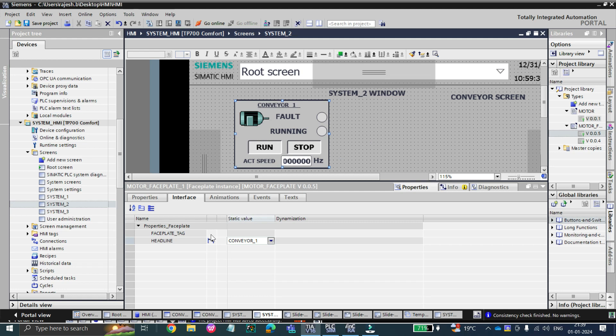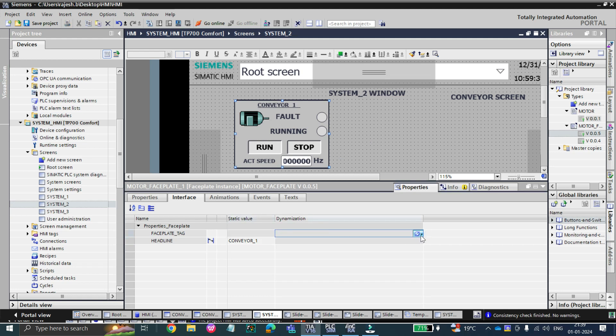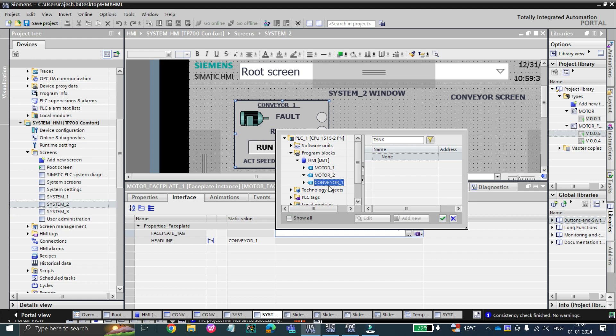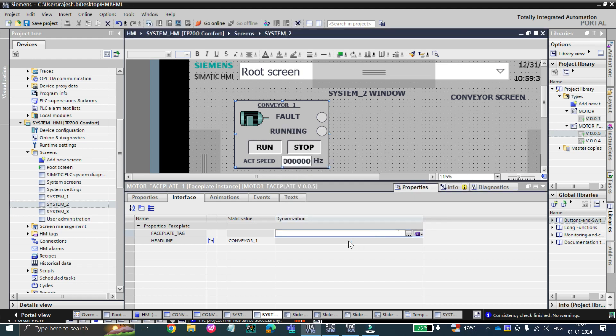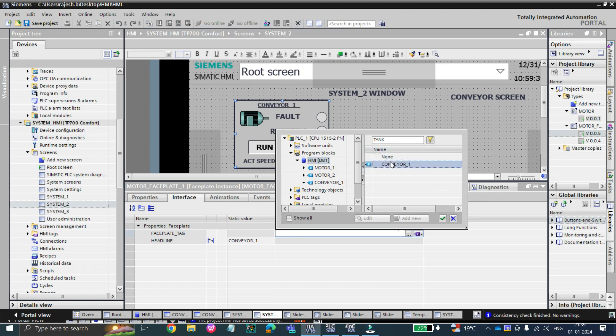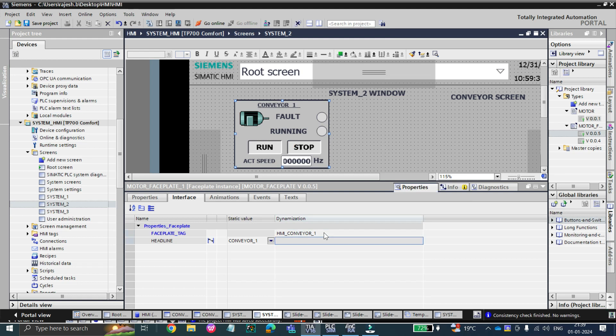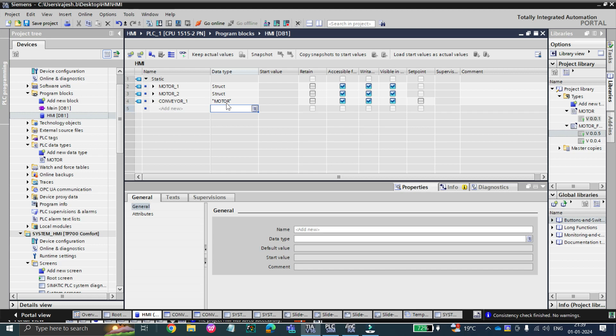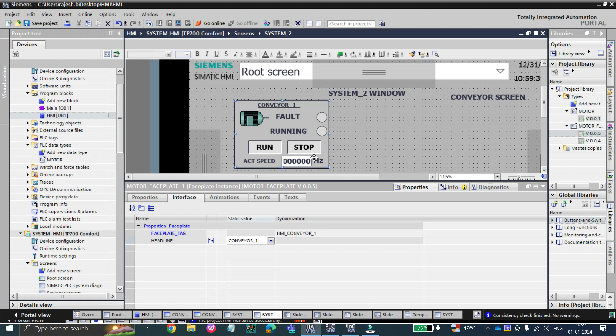Let's delete the old setup. We will do faceplate one first, then faceplate two. Now you can connect the data types at the HMI tag — go to conveyor 1 and HMIDB conveyor 1 and directly select it. What will happen is all the internal tags will be directly connected to this tag. Remember, at both times the tag has to be the same: whatever data type is in the faceplate — the motor data type — it also has to be the motor data type in your HMI data block.